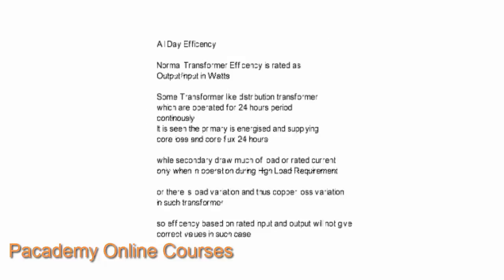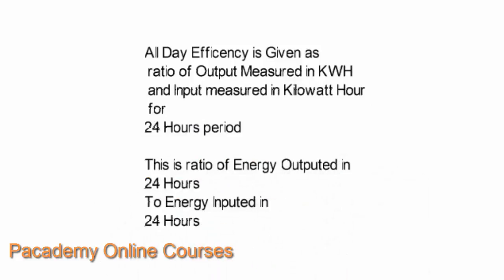To find out the efficiency of such transformers accurately, the all-day efficiency method is used. All-day efficiency is given as the ratio of output measured in kilowatt-hours to input measured in kilowatt-hours. The output energy and input energy of the transformer during 24 hours are taken, and their ratio gives the efficiency of the transformer. This is the ratio of energy output to energy input over 24 hours, and is how efficiency is found mainly for distribution transformers.